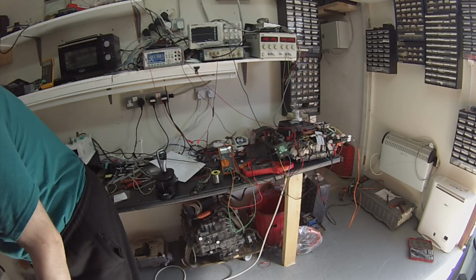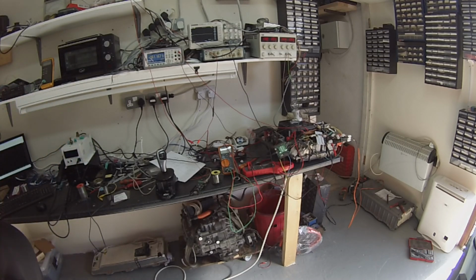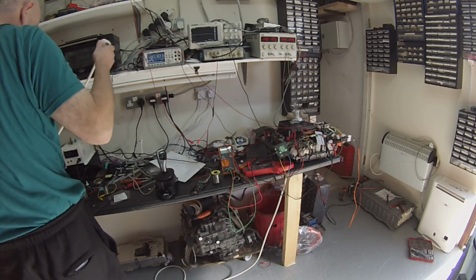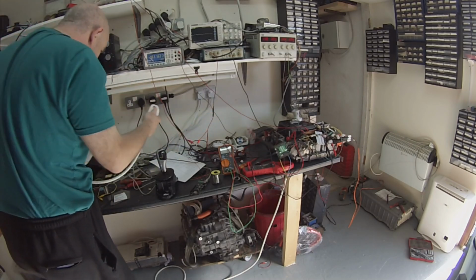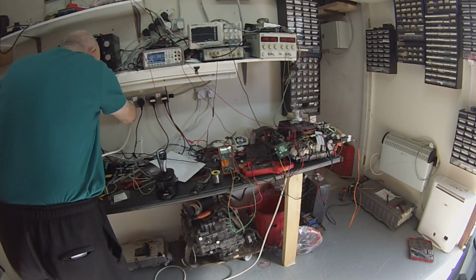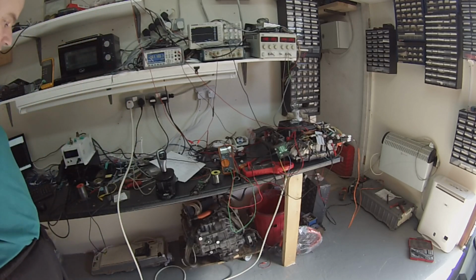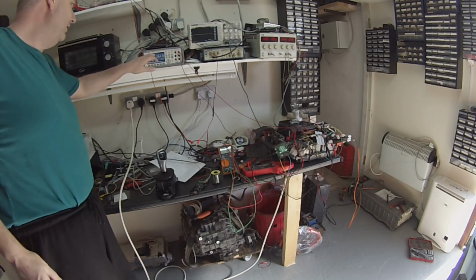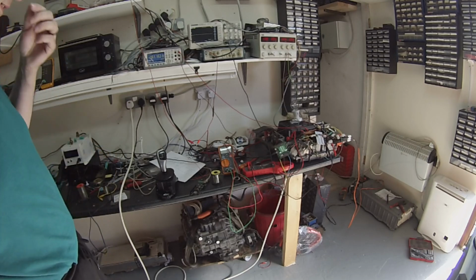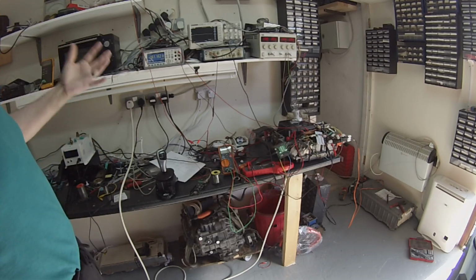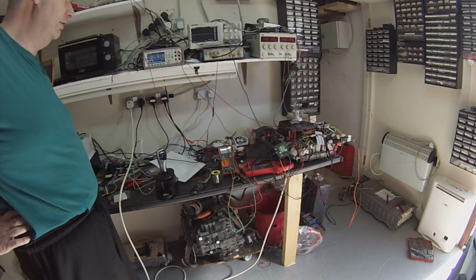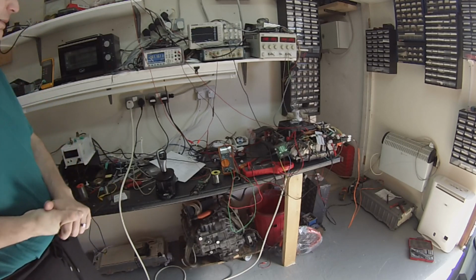What we don't want to do is to simply take our AC power, plug that in, and throw the switch, because we've got a discharged capacitor here, and if we throw that, that's going to blow a fuse or trip a breaker or cause some kind of damage.